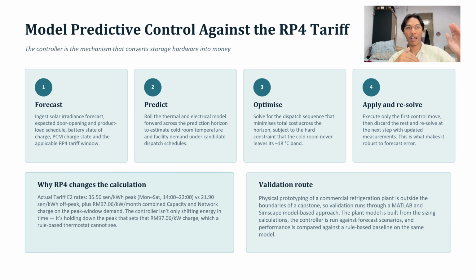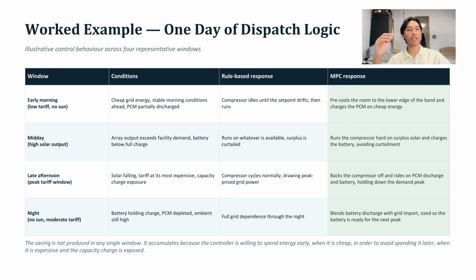So we want to vary usage during the time of day, so we can control how much cost we save. There's the morning, midday or afternoon, but I'm going to focus on the late afternoon, the most expensive tariff window. This window sets our capacity charge for the whole month, basically. A basic system just keeps cycling normally and pays the full price, right? So our compressor turns off and we use the PCM and battery instead during that time, so that we don't use a lot of electricity from the grid during peak hour. So we save more money and use the grid during the times that are not as expensive.